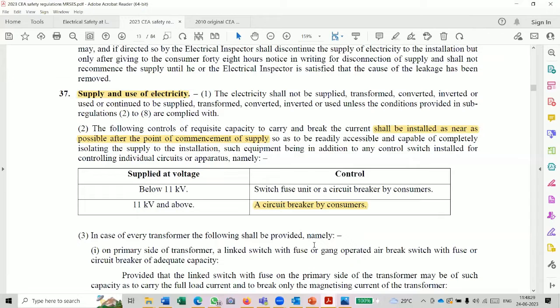And if you are putting up the breaker on a pole, that is outdoor type, even then the cost difference is very big. A VCB outdoor type will cost around 2.25 lakhs, whereas a simple AB switch with the dropout fuse will cost only some 35,000 rupees. So there is a definite issue in 37.2.3 with regard to MSMEs and small entrepreneurs.